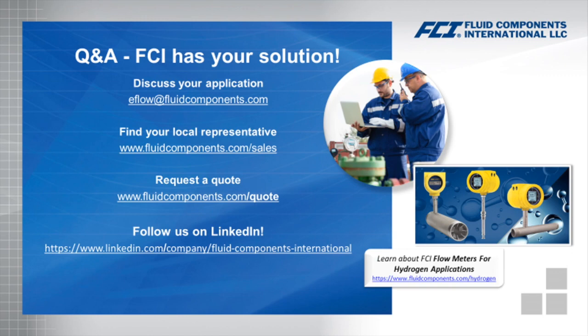When done properly with the calibration facilities, using an actual gas, your pressures, temperatures, and actual velocities are really part of that calibration itself. So it really comes down to your confidence in that manufacturer and their ability to properly calibrate the instrument.